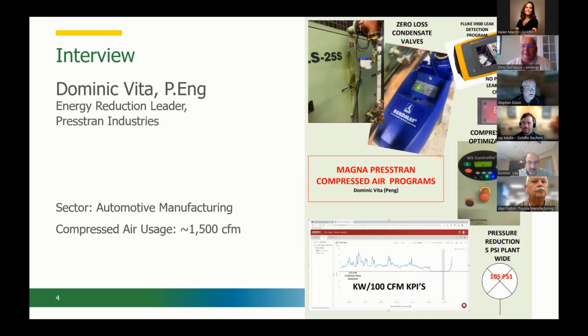So that's where the optimizer would work. Yeah, I agree. And the other thing to keep in mind is that variable, once it hits full load, is probably going to use marginally more energy than the fixed speed, because of the drive in there. It's only a couple of percent, but it's not going to be as efficient at full load because of the drive electronics in there too. So that's the other piece that enters into it.